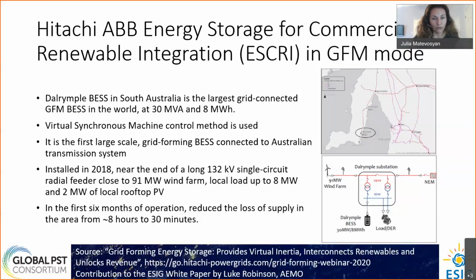In the first 6 months of operation, it's shown that this project reduces loss of supply in the area from 8 hours to 30 minutes. So it helps when interconnection with the rest of the grid is lost, then this part of the grid is being operated as an island, and this way supply is retained to customers.